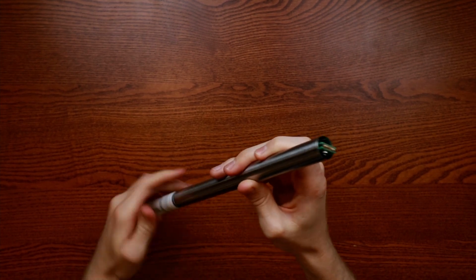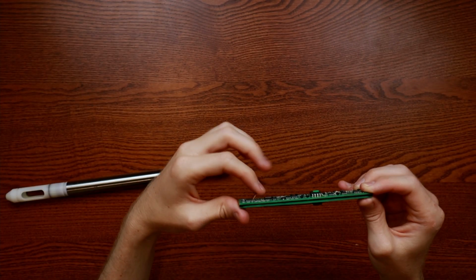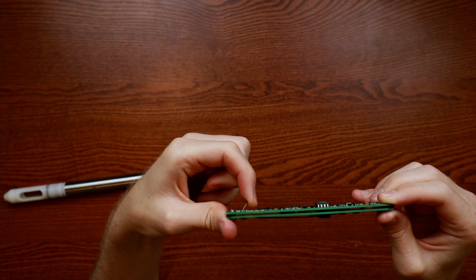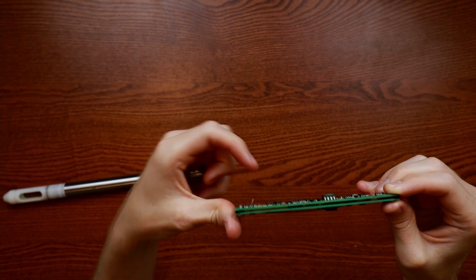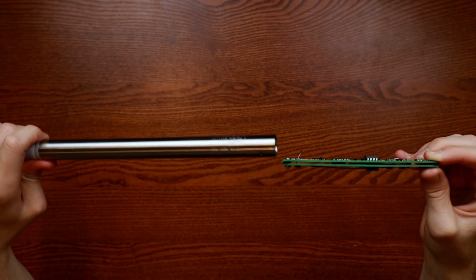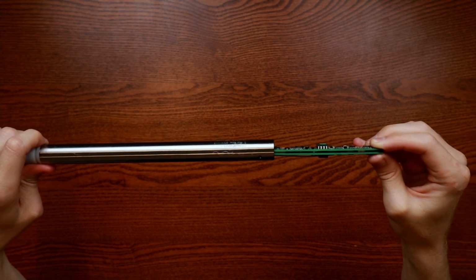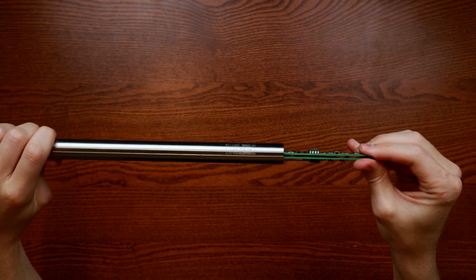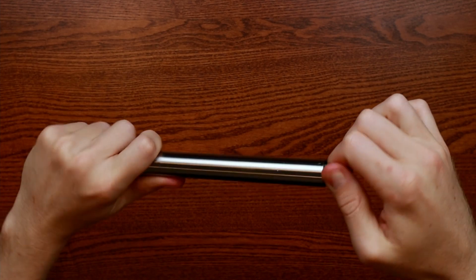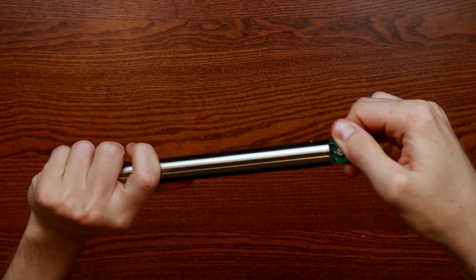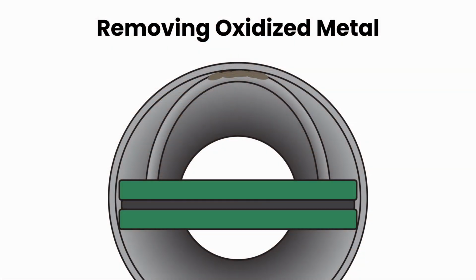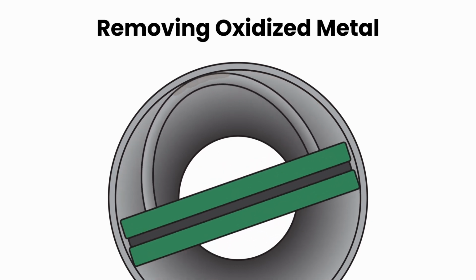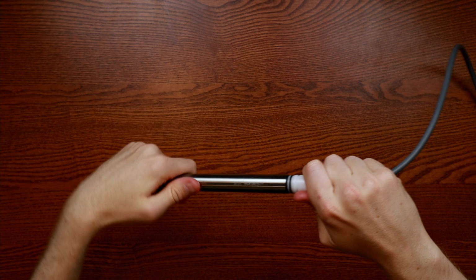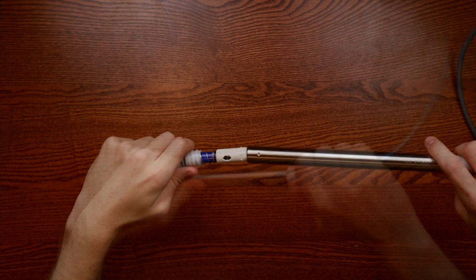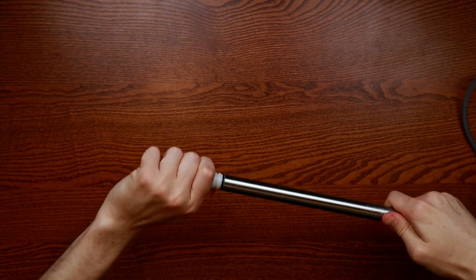board can be grabbed. Once you have the circuit board out, lightly bend the solution ground wire upward. Slide the circuit board back in while avoiding the dimple and verify the wire is contacting the housing. While still holding the circuit board, twist it back and forth to scrape the wire against the housing. This removes any oxidized material from the surface of the solution ground wire. Once the circuit board is back in the housing, reinstall the cable connector, then reinstall the electrode. Test and see if this fixed your problem.